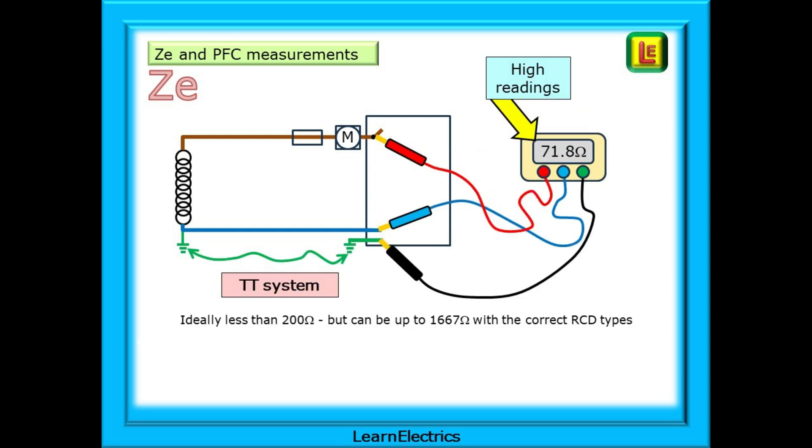For TT systems there is no copper earth connection between the installation and the supply transformer. We rely on the earth rod at each end and the conductivity of the soil to allow the fault current to flow out of the installation earth rod. What flows out is replaced by electrons flowing in at the transformer earth rod. This does mean that ZE is very much affected by the conductivity of the soil and the distance to the supply transformer. The readings shown here would have been typical for my house out in the wilds of Shropshire in the winter, but a long hot summer would see the impedance rise as the soil dried out. Ideally we are looking for readings below 200 ohms, but this can be extended to 1667 ohms if the appropriate RCDs are installed.